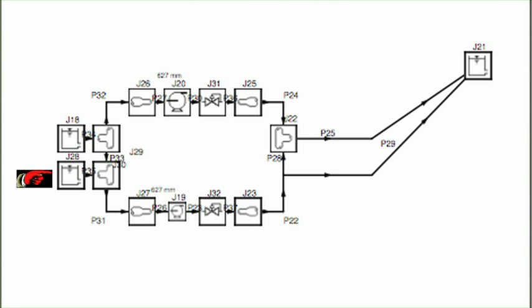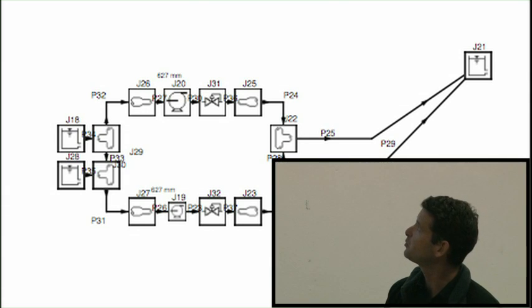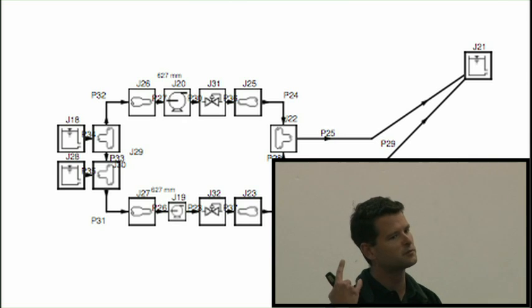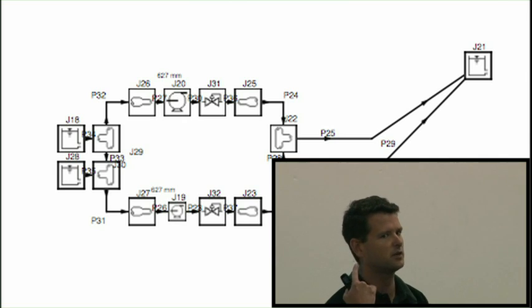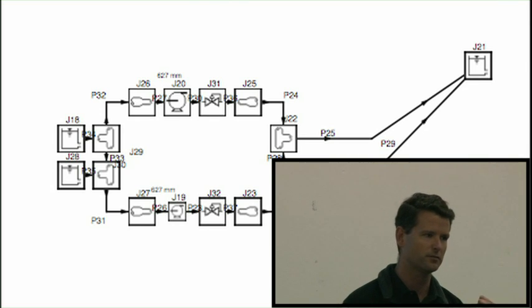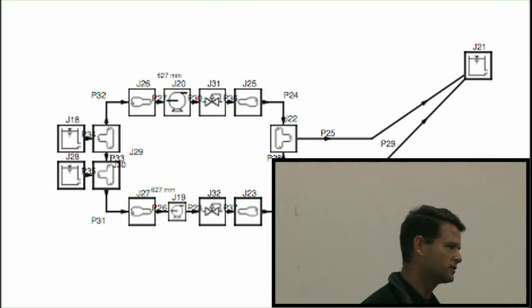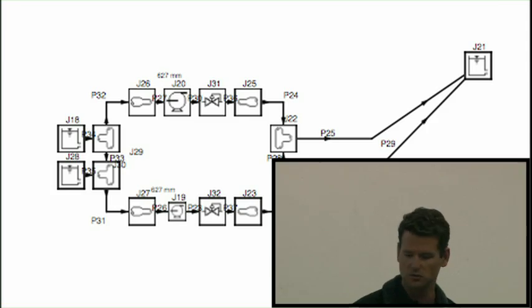We modeled one new pump to match the existing big silver pump. Upgrade this one so that they're both the same size, 630 kilowatt motors instead of the existing 400 kilowatt motor. Control valves to control the mill reservoir level, because you can't be switching these things on and off too much. We're really going to be aiming at twice a day. And we're going to put in a mill telemetry system to monitor the mill level. What they were previously doing is they were phoning up to the mill reservoir, and they would say, well, what's the level? And the guy would say, oh, well, I'm 95% now, so they'd switch one of the small pumps off. And a while later, they'd get a phone call and they'd switch another pump on, and they'd just play with switching the smaller pumps on and off.